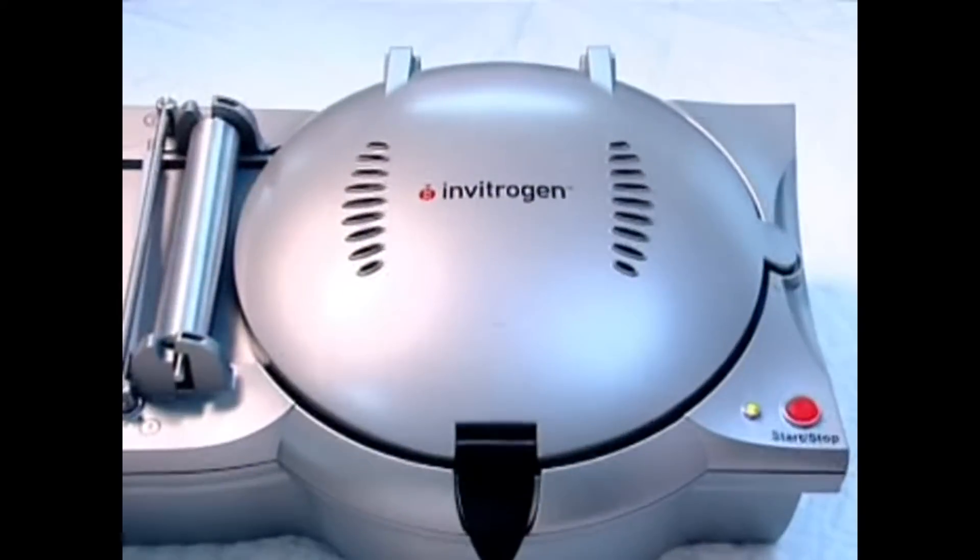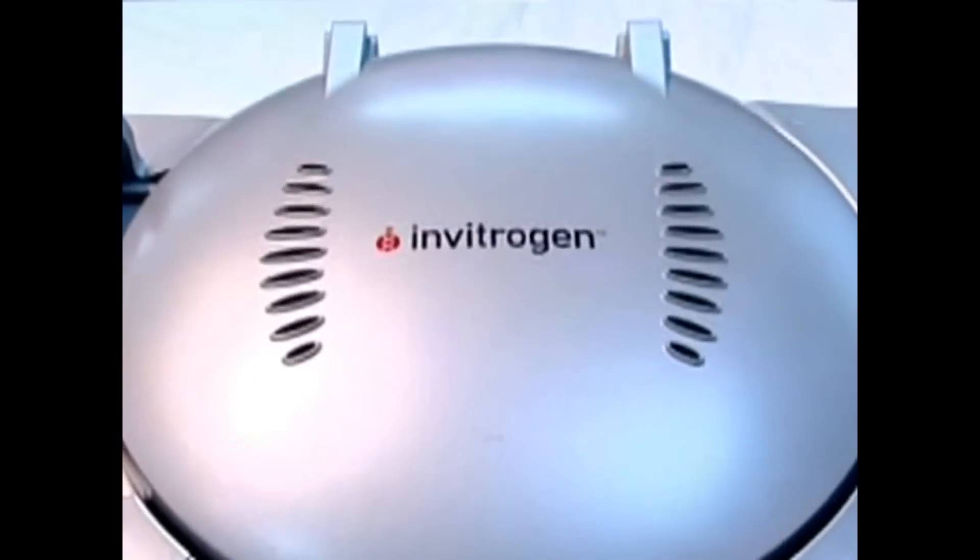This revolutionary dry electrode blotting technology is based on a simple concept. The separation gel is sandwiched between two ion reservoir matrices which absorb the ion products of electrolysis at the electrodes and replace them with current carriers.